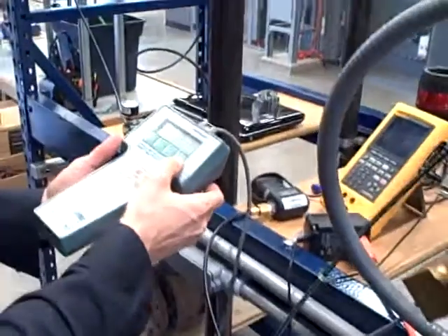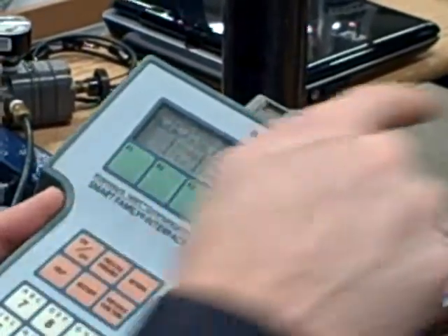Okay. Analog output outside range points. Well, that's fine. We'll just override that. It thinks it's reading 30.045 psi. We are actually applying 30.014. It's not quite stabilized yet.